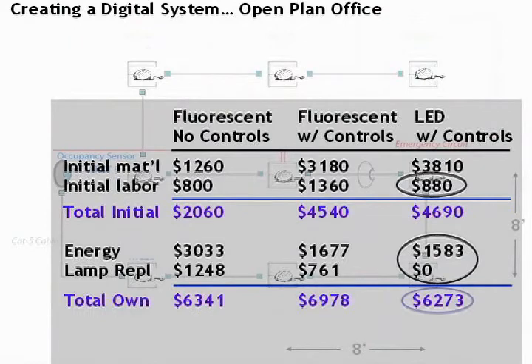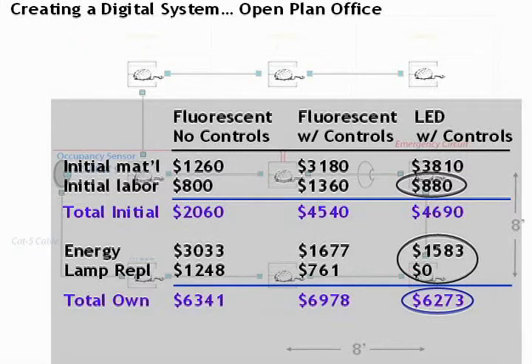So if you total all that up at the end, what you see is that all three systems end up coming out very close. The fluorescent system with no controls, in terms of total owning costs over a 15-year life cycle, is high because of the annual energy and lamp maintenance costs. The fluorescent with control system is higher because of the initial cost, but has improved operating costs. And then the LED with controls actually comes in very close to the fluorescent in terms of installed cost, but has a great benefit in terms of energy performance and lamp maintenance.